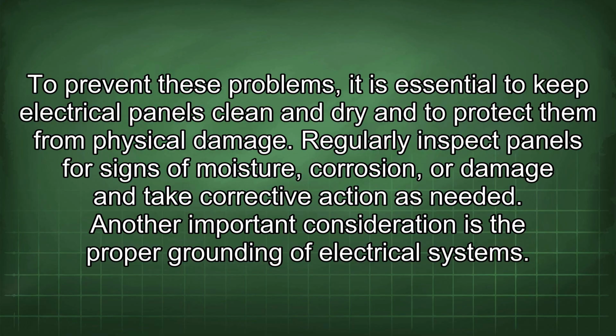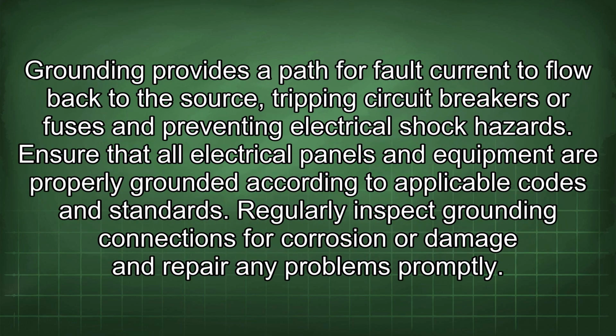Another important consideration is the proper grounding of electrical systems. Grounding provides a path for fault current to flow back to the source, tripping circuit breakers or fuses and preventing electrical shock hazards. Ensure that all electrical panels and equipment are properly grounded according to applicable codes and standards. Regularly inspect grounding connections for corrosion or damage and repair any problems promptly.